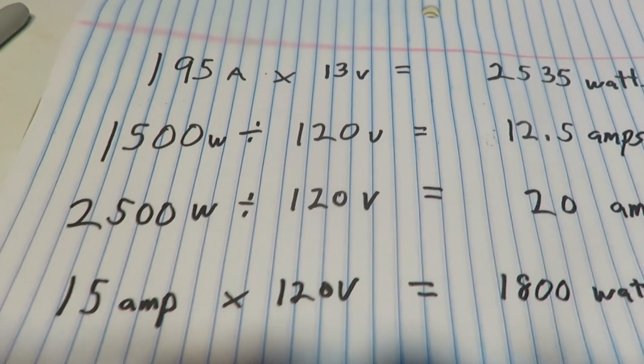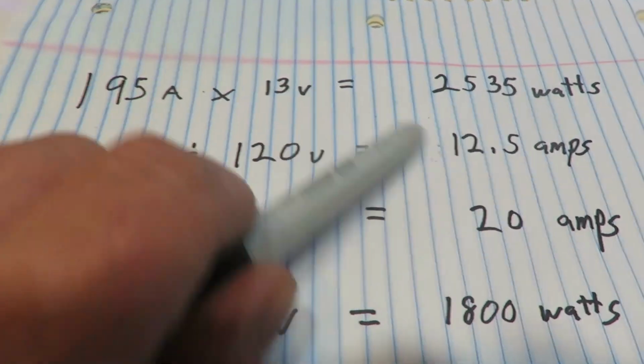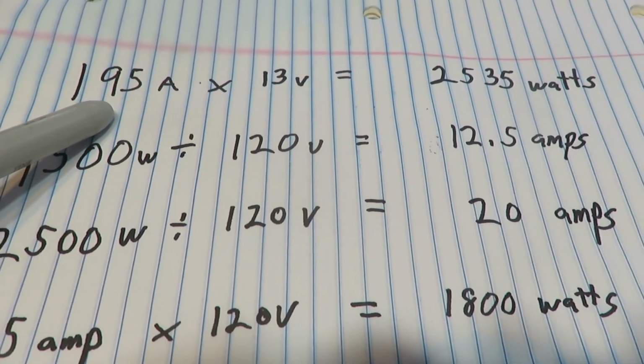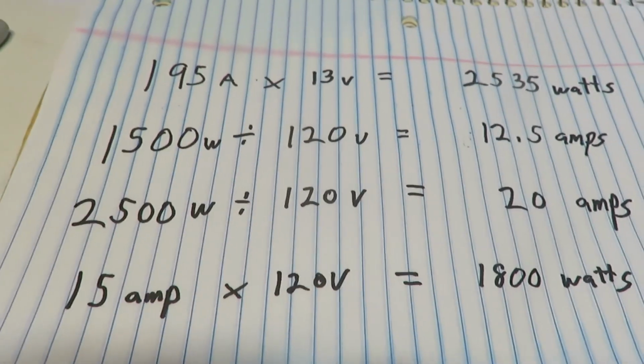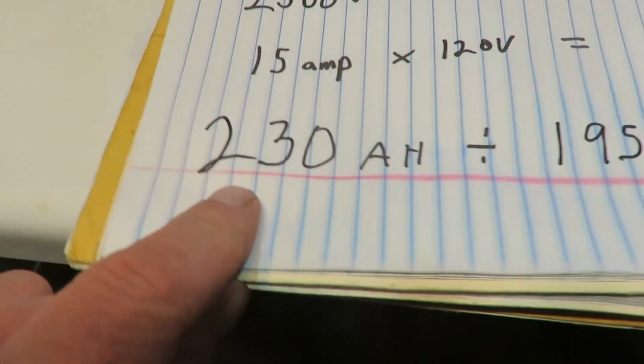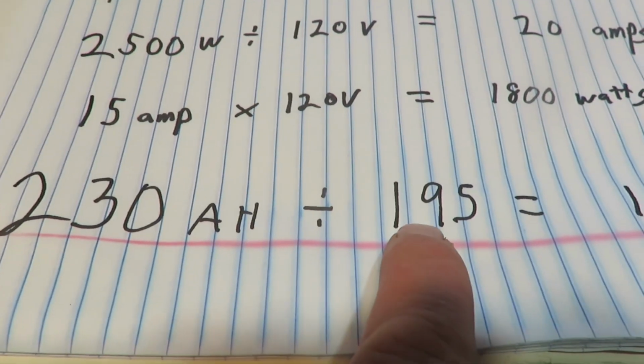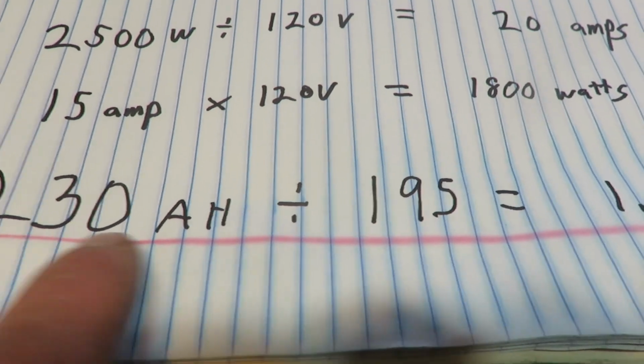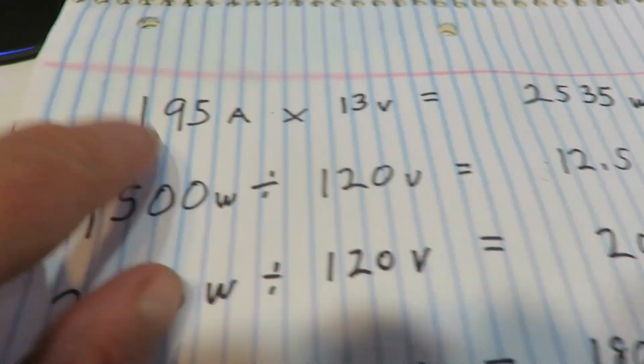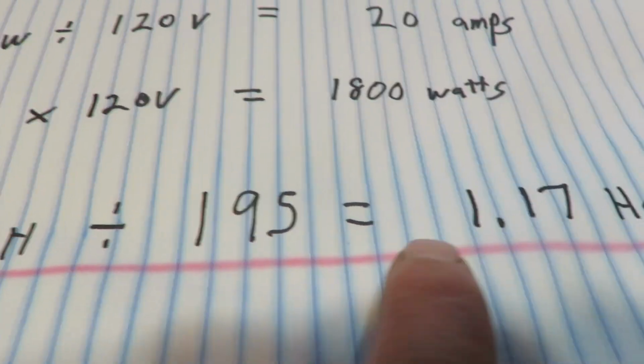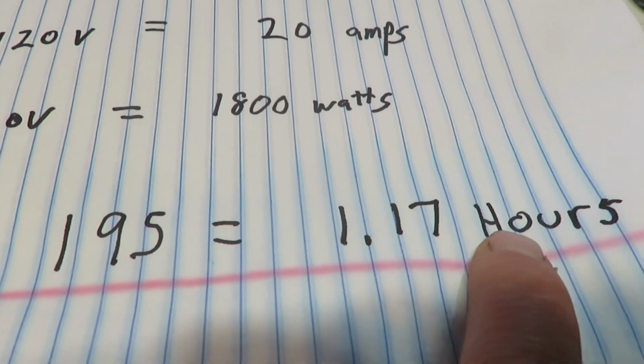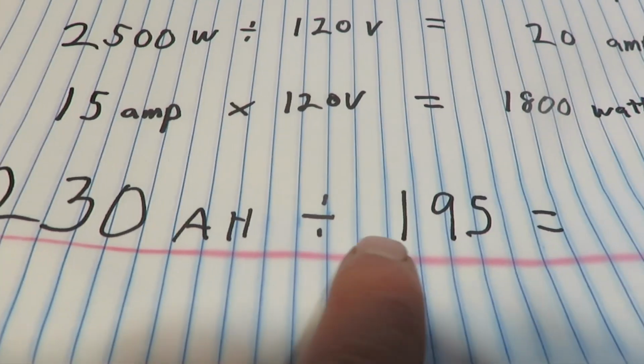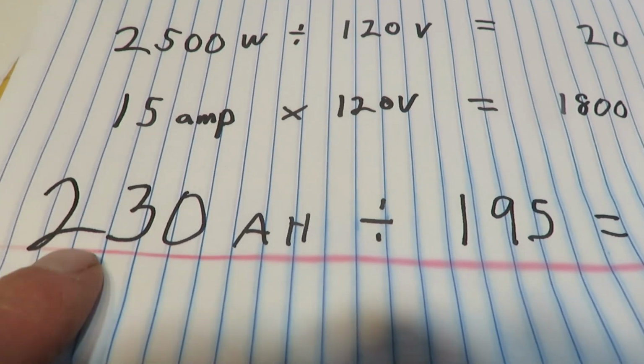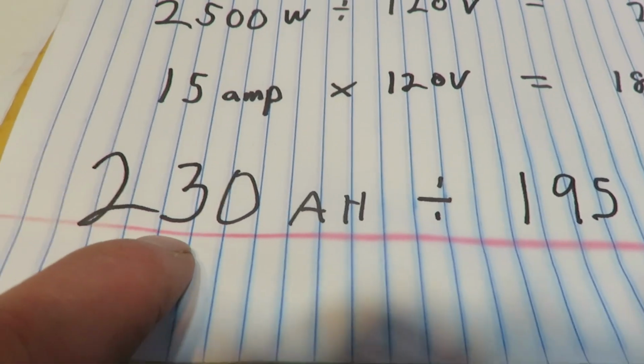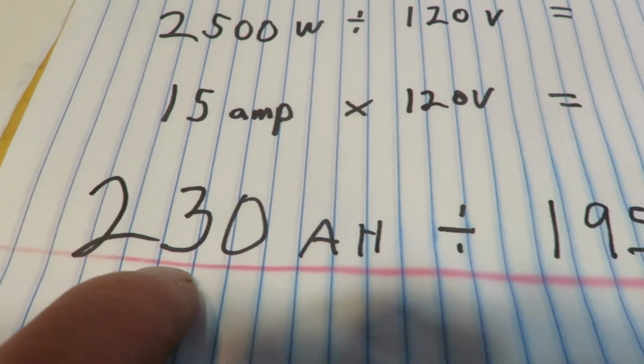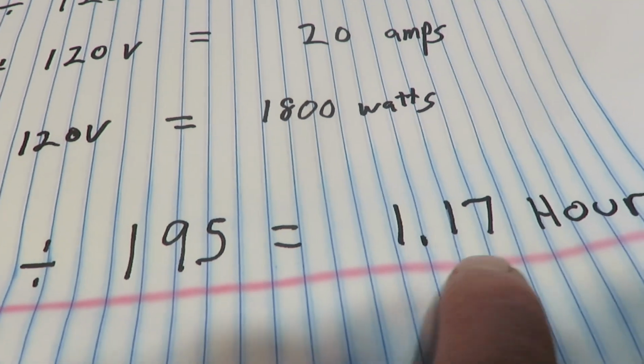And then I didn't do the calculations of how long that battery would last if you were running full loads. I can do that. Okay, I did this calculation. 230 amp hour battery divided by 195 amps. If you were to take the maximum out, of course, not 195 because you'd want to stay under the 200. Then that would last you 1.17 hours. But in reality, you can't get that much out of it, because you're not going to take 100% out of this battery. Maybe if you're lucky you can get 80% out of it. So multiply this number by 0.8.